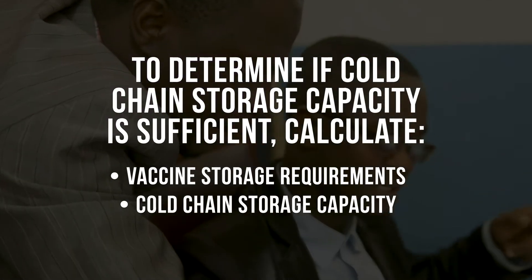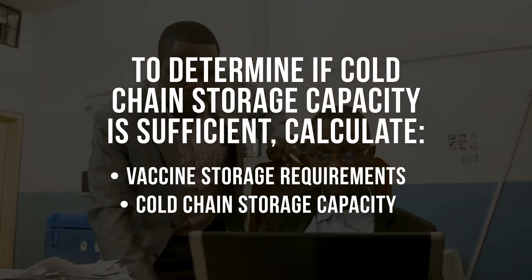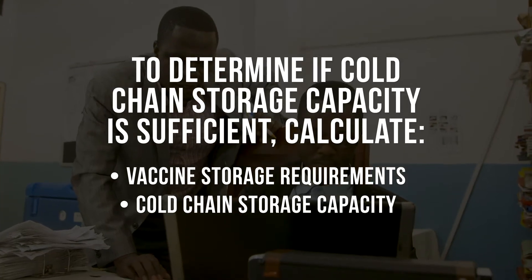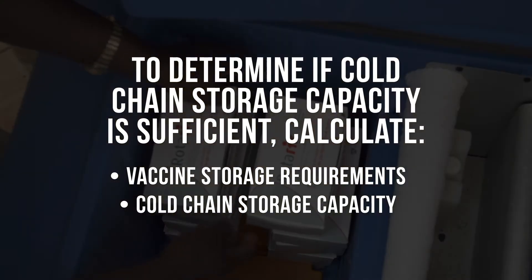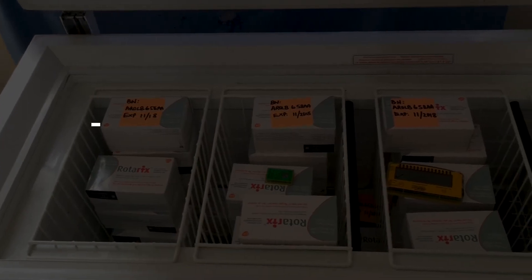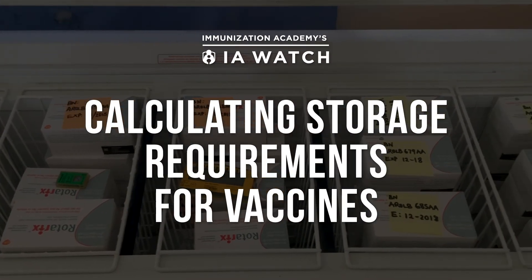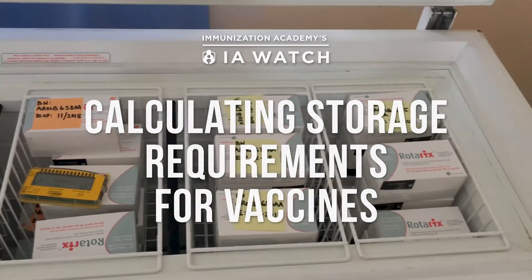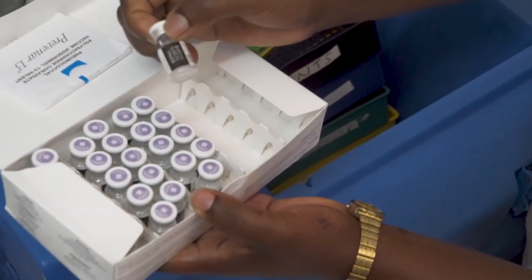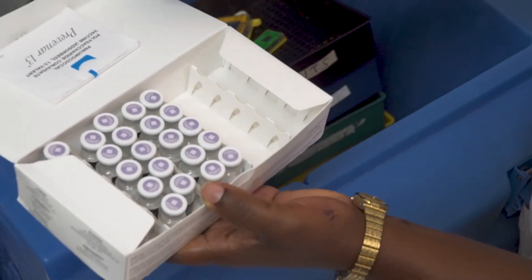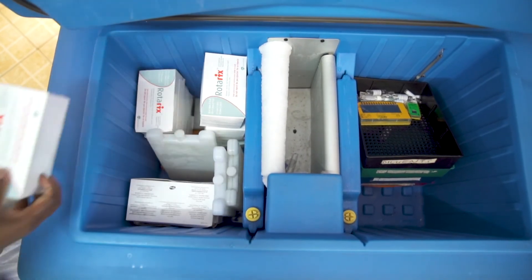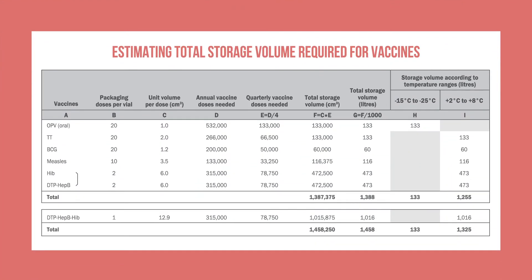If the storage volume required for your vaccines is greater than your existing cold chain storage capacity, you have a capacity issue that will need to be addressed. In this video, we will focus on calculating storage requirements for vaccines. To calculate the vaccine storage requirements, you will calculate the storage volume needed for each type of vaccine expected and then add those estimates together. Let us use this table to walk through the calculation.